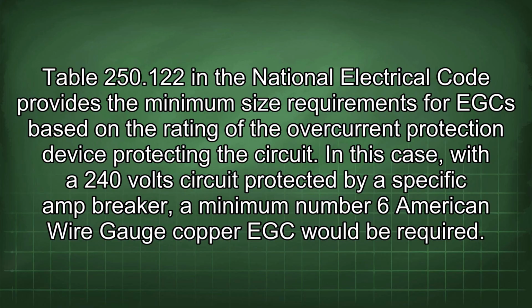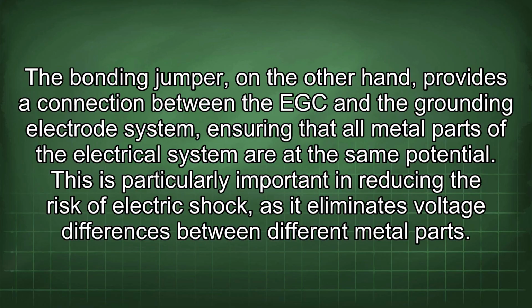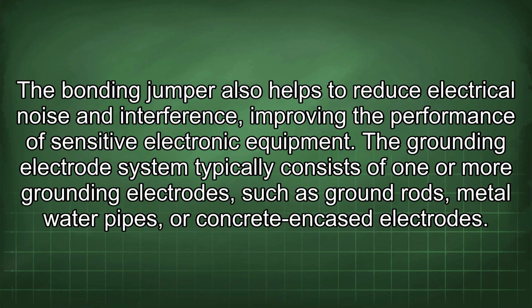Table 250.122 in the National Electrical Code provides the minimum size requirements for EGC based on the rating of the overcurrent protection device protecting the circuit. In this case, with a 240-volt circuit protected by a specific amp breaker, a minimum number 6 American wire gauge copper EGC would be required. The bonding jumper, on the other hand, provides a connection between the EGC and the grounding electrode system, ensuring that all metal parts of the electrical system are at the same potential. This is particularly important in reducing the risk of electric shock, as it eliminates voltage differences between different metal parts. The bonding jumper also helps to reduce electrical noise and interference, improving the performance of sensitive electronic equipment.